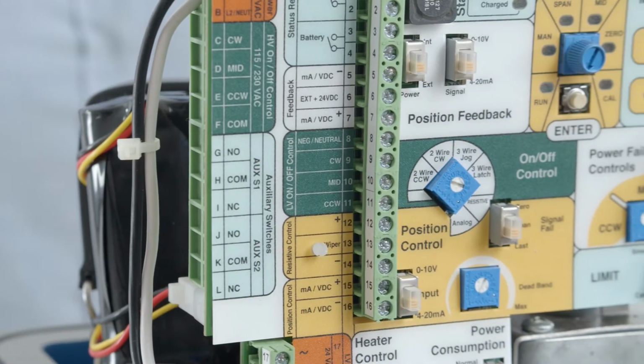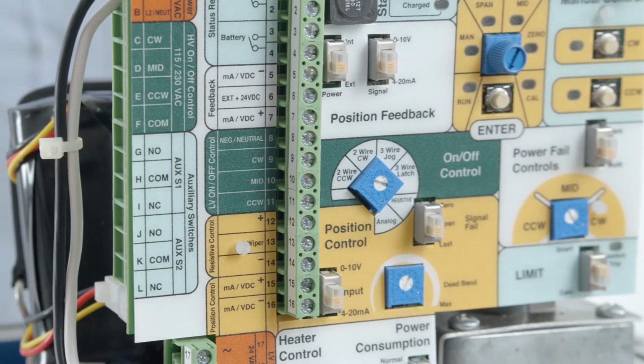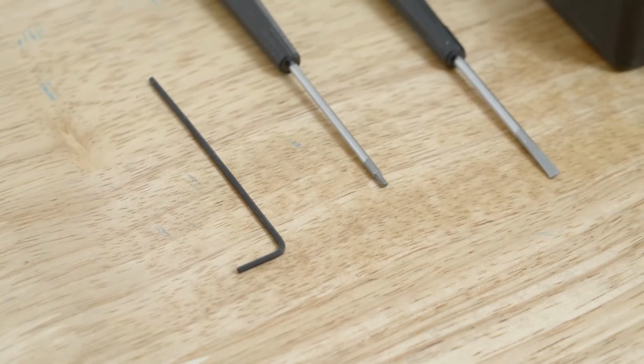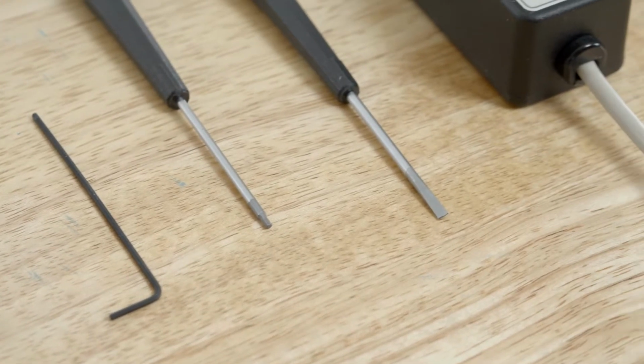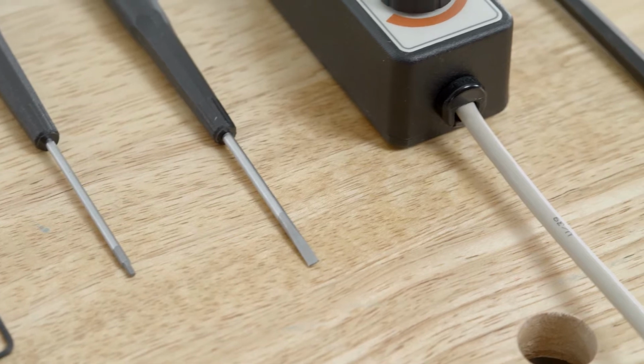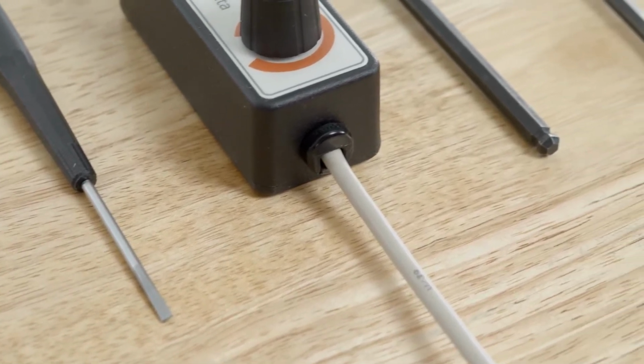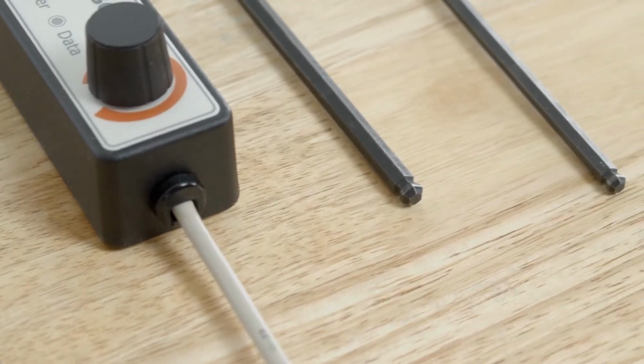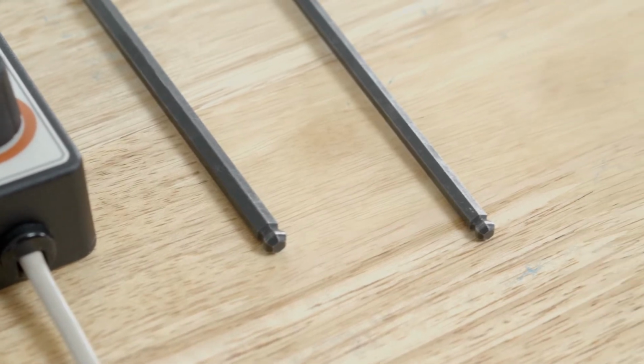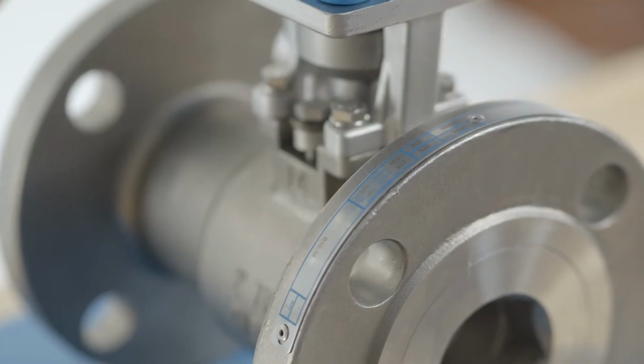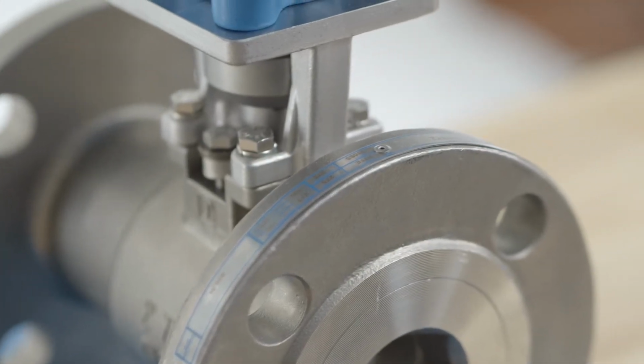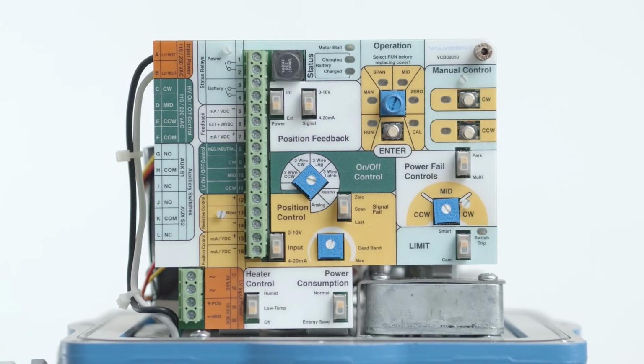Dangerous voltages are present inside the actuator. Please use extreme caution when working on the actuator with the cover removed. For portions of the following procedures, you will need a 1/16 hex or Allen head wrench and a small flat blade screwdriver. Depending on the desired control method, you will also need a 4 to 20 milliamp signal generator. The instructions in this video assume the cover of the actuator has already been removed.